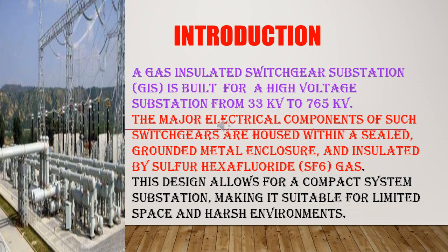Basic description of Gas Insulated EHV Substation. A Gas Insulated Substation, GIS, is a high-voltage substation where the major electrical components are housed within a sealed, grounded metal enclosure and insulated by sulfur hexafluoride, SF6. This design allows for a compact footprint, making it suitable for space-constrained areas and harsh environments.